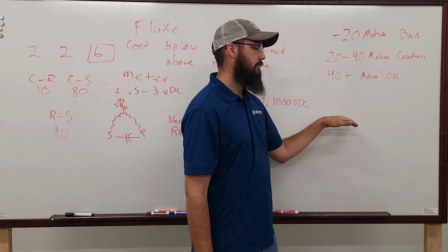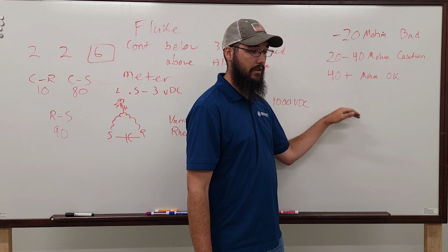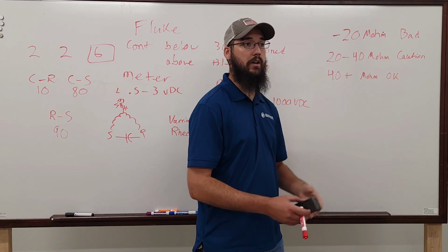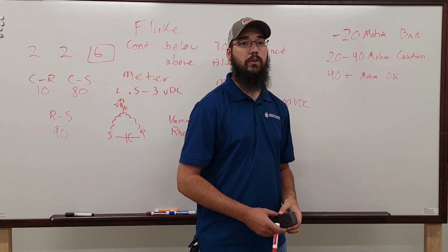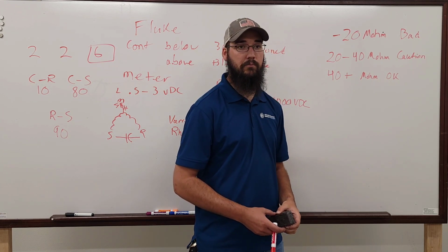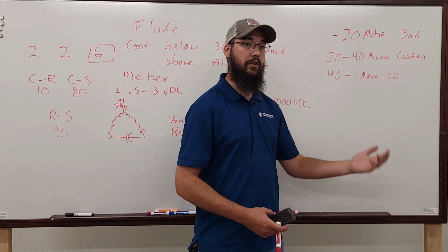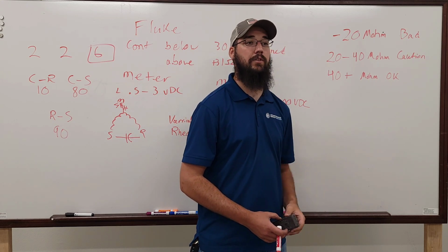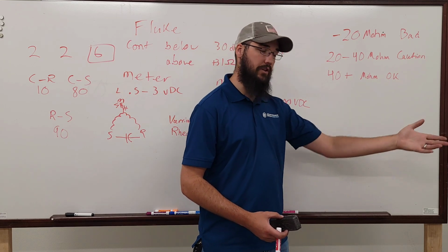Because of that, I'll start to see that, between annual maintenances, that'll decrease. So say I walk in one year, it's got 1.5 billion ohms, okay? A year later, I've got 1 billion ohms. A year later, I've got 800,000 ohms. Same thing with the vibration readings.